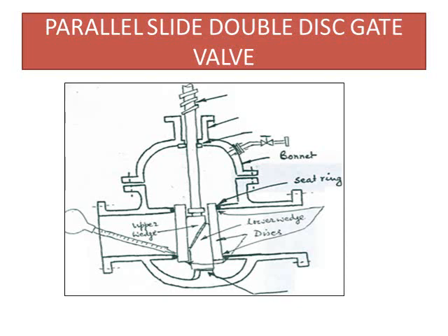If in any case the valve shall pass, only the high pressure liquid which is sent through the bonnet inside of the valve shall pass through the valve, and your hazardous liquid or toxic liquid will not be allowed to pass through the valve. Therefore, these valves are very safe in industries where toxic or hazardous liquids or any precious liquids are handled which are not to be allowed to leak into the atmosphere.